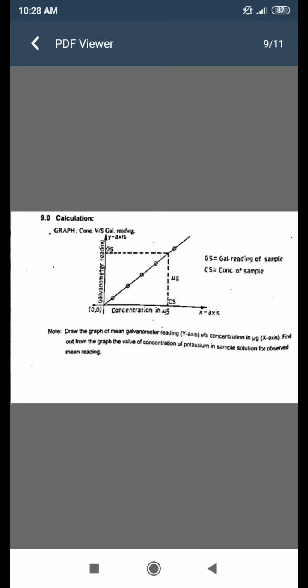The concentration values are 90, 180, 270, 360, and 450 micrograms, with the sample concentration being unknown. For calculations, draw a graph of mean galvanometer reading on the Y-axis versus concentration in micrograms on the X-axis. From the graph, find the concentration of potassium in the sample solution for the observed mean reading. Gs is the galvanometer reading of the sample and Cs is the concentration of the sample.